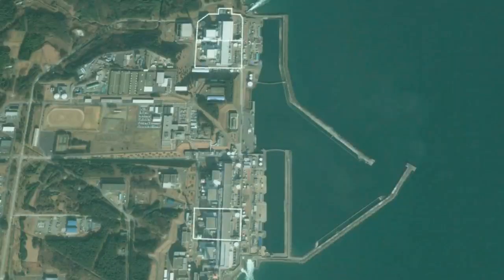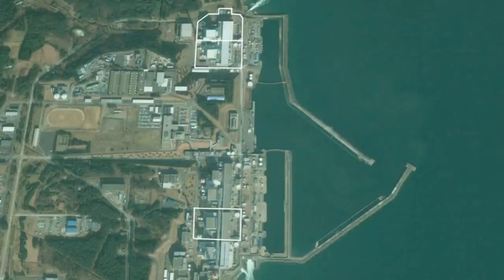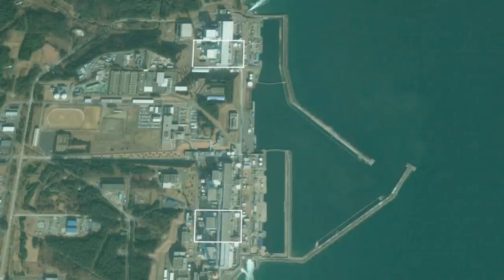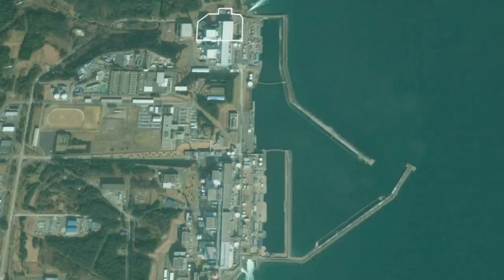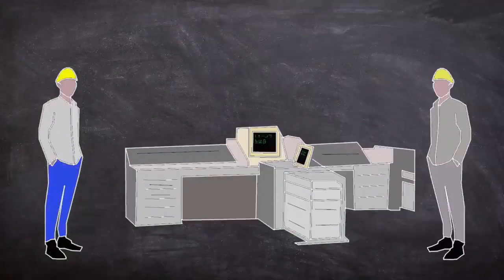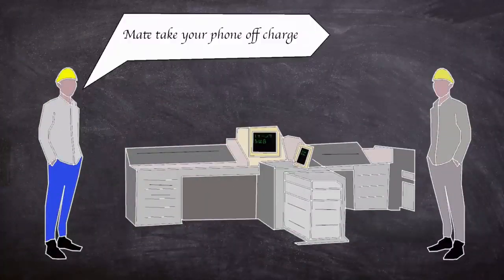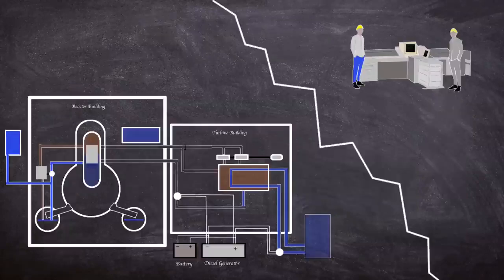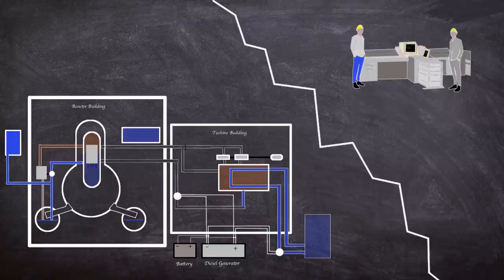Units three, five and six maintained power allowing the operators to observe the power status as the main control room indications and controls were still functioning. Units three and five still had DC battery power and six still had full AC power. To extend the time between full plant blackout on units three and five all non-essential systems were shut down. In unit three the operators manually restarted the reactor core cooling system controlling and monitoring the reactor water injection with the available DC power.